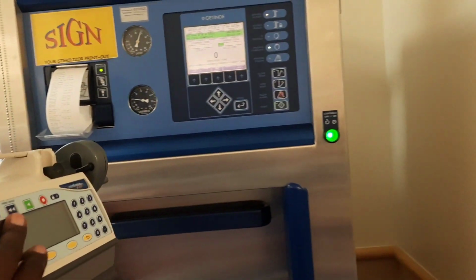Okay, 3 o'clock in the morning. We're going to go and get the test, the dart test that we did. And this hospital, like I said, is a campus, so they have many ORs. So they have these little sterilizers that are close to the OR. If the doctor drops something, or if anybody drops anything that they need for the case, and they cannot wait, you see how long? 65 minutes. If they can't wait that long for that one little instrument while the case is going live, they will flash it. And flash is just flash quick. So they have about 10 of these small ones.